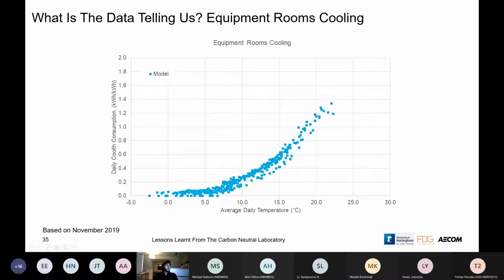And you can see all this free cooling we're getting from the fresh air down here. Because the density of some of these rooms is quite high in terms of equipment, it starts to rise up when the temperature is fairly low, but we're still getting free cooling. So wherever the value is below 1, we're basically getting free cooling out of the fresh air. And when it goes above 1, we are having to put more cooling in than the actual space demand to cool the outside air temperature down as well.